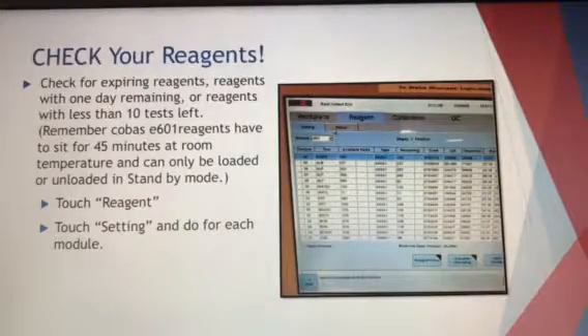While the instrument is going into standby, you can actually check over your reagents, and it's very important to do this so we don't have to stop during the day. Just use your best judgment in picking which reagents we need to unload and which reagents we need to put on, because there are only a certain number of slots that the instrument will hold, so it can only hold so many. But a good clue for taking some off and replacing would be ones that are expiring, that expired that day, or with 1 day remaining before they expire.